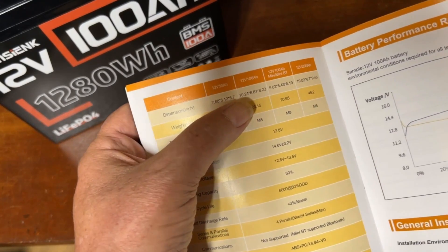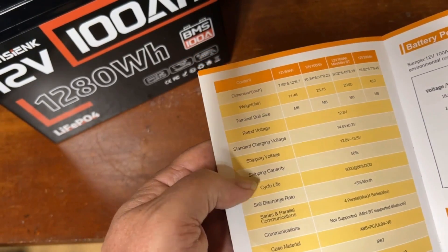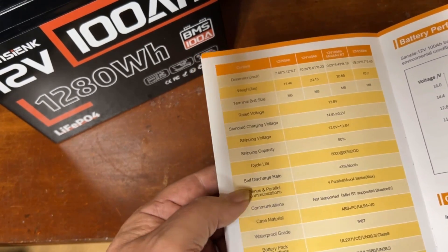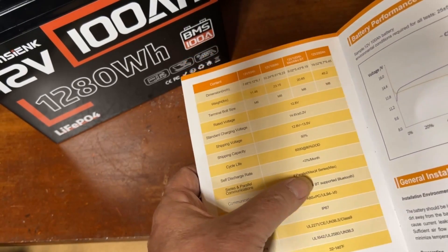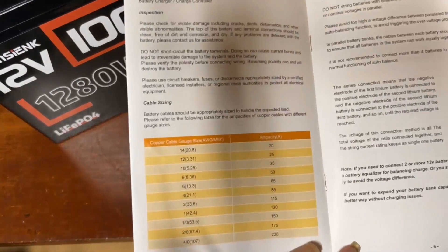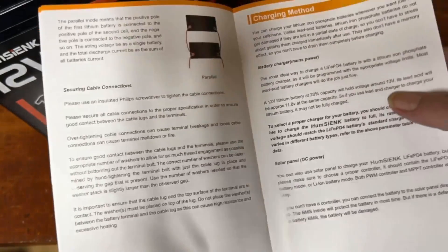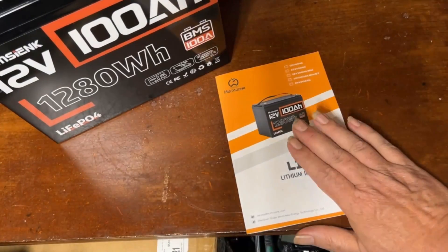It has all the typical protections including low-temperature discharge and charging protection. Dimensions are 10.24 by 6.61 by 8.23 inches. Cycle life is 6,000 at 80% depth of discharge. Self-discharge is less than 3% per month. You can run four in parallel and four in series. This is not the Bluetooth model — they do have a Bluetooth version. The manual also covers performance discharge curves, cable sizing recommendations, parallel and series hookup, charging methods, and troubleshooting. It really is an excellent manual.